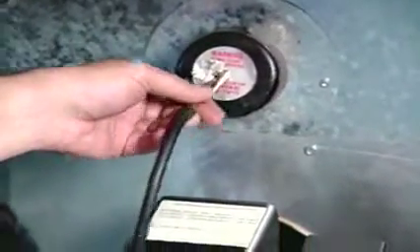For complete combustion to take place, there must be enough primary air present. Check the furnace combustion process by measuring the overfire draft and the stack draft. In addition, check the smoke number of the flue gases. The combustion gas indicates a zero smoke reading.